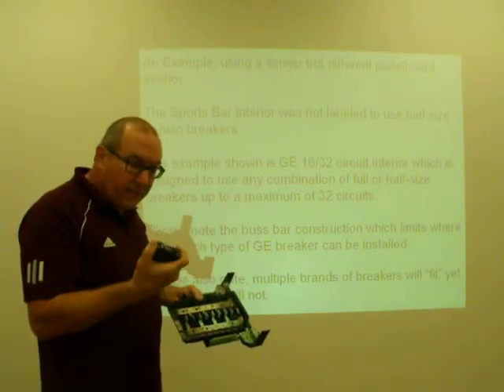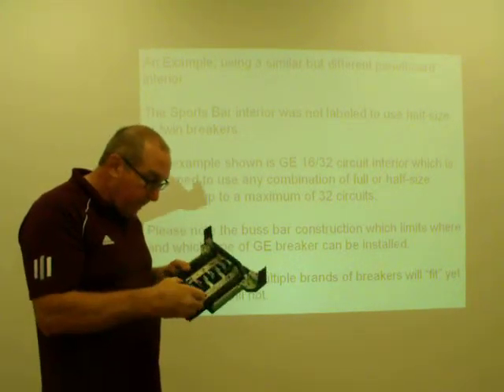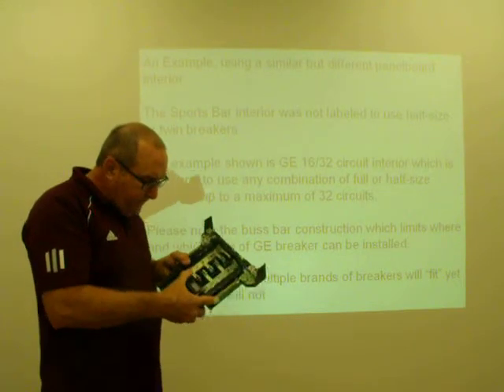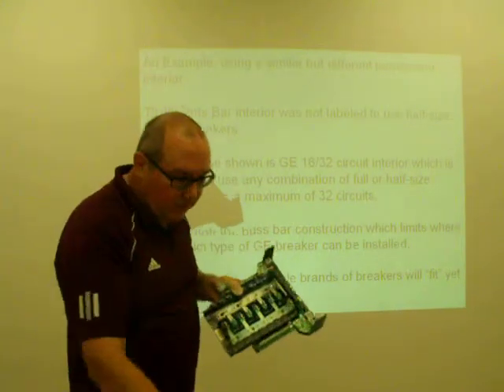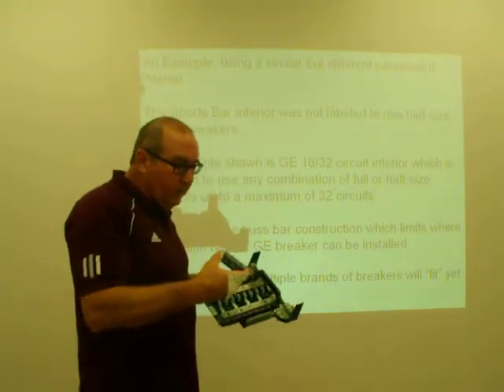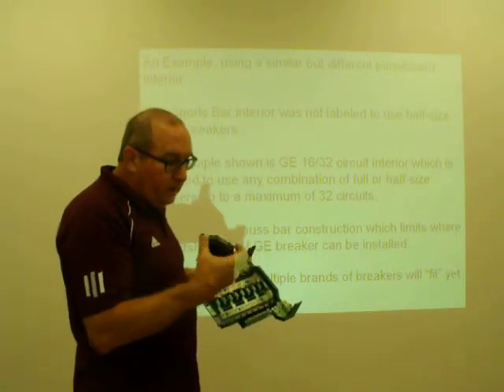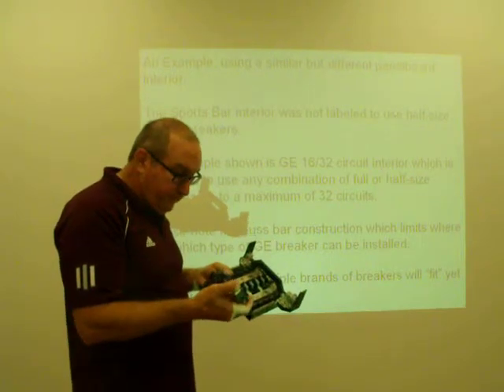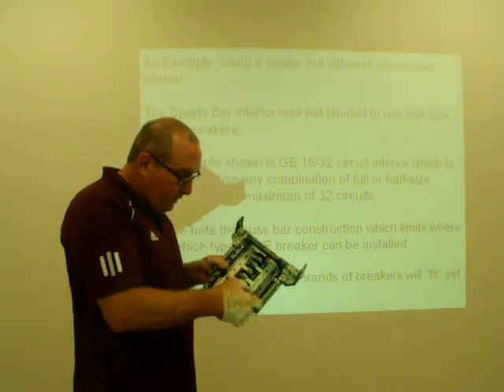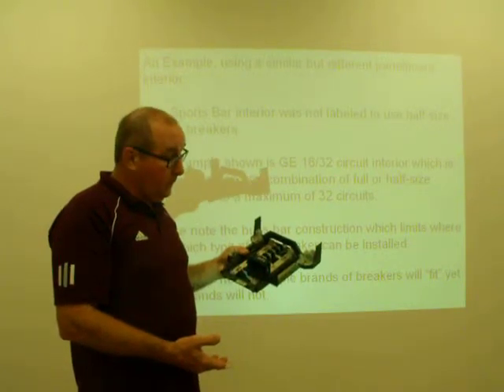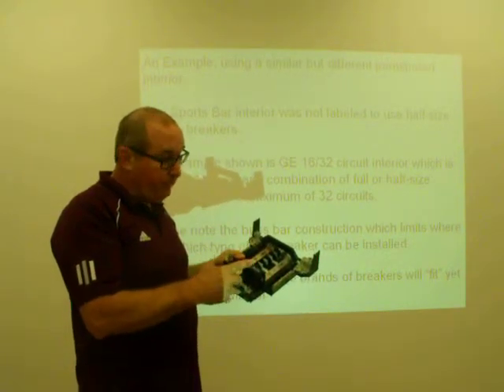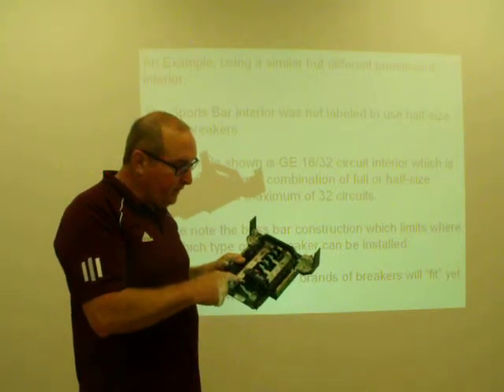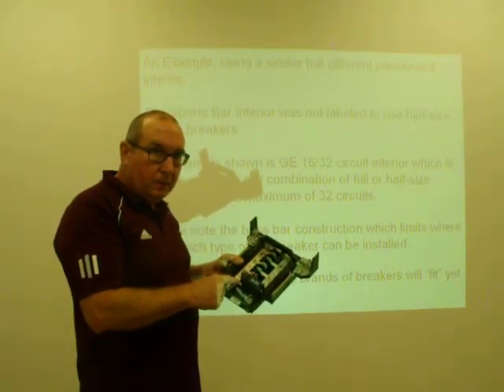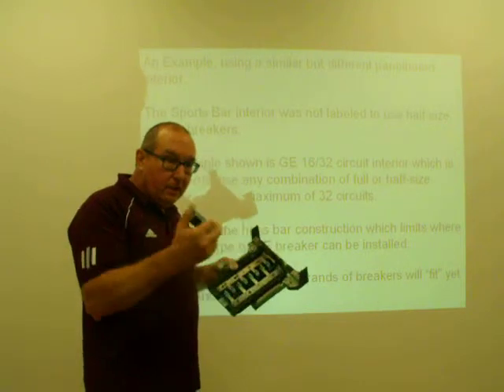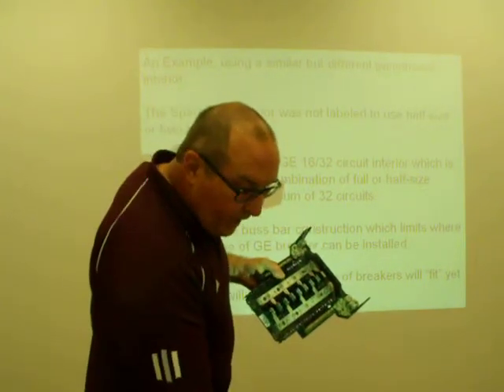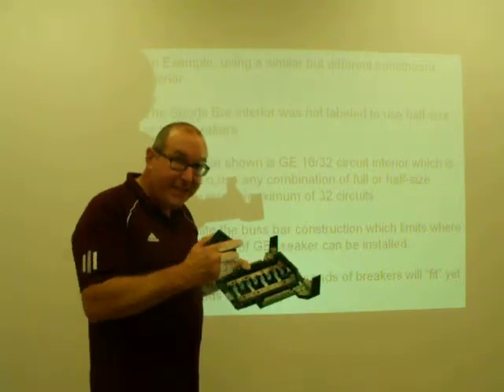This is an ITE breaker, a company that is out of business. It will physically not fit. That's a good thing. This is a Thomas & Betts. I'm not sure they're still in business doing that. It fit. Does that mean that it's legal, safe, code compliant to use this Thomas & Betts breaker in this GE panel board? Certainly not, unless this breaker has information documenting that it has been UL tested and accepted for that use.